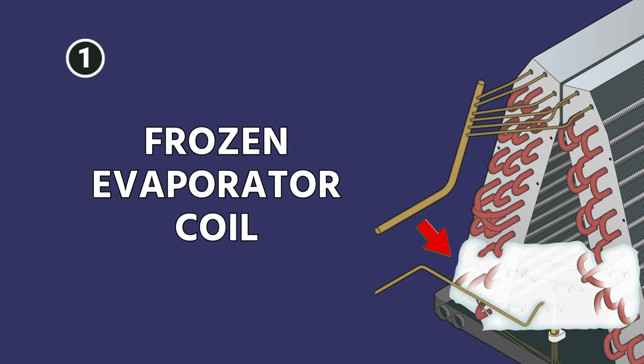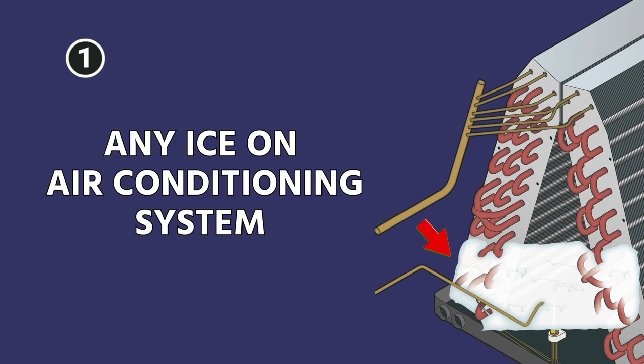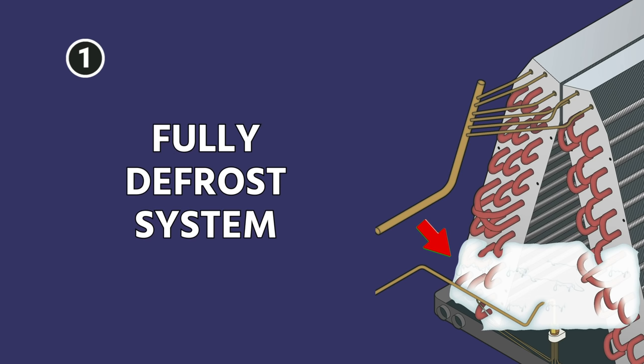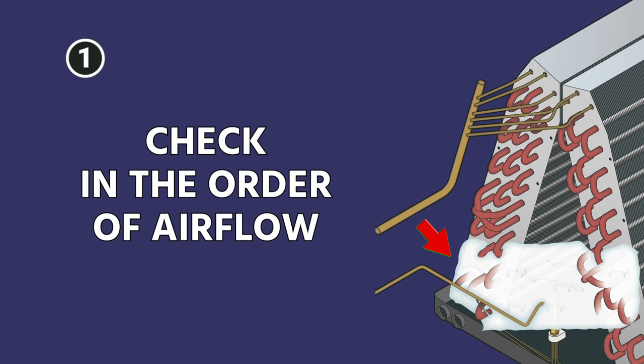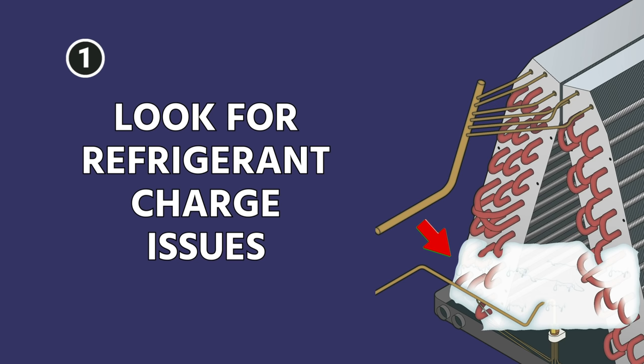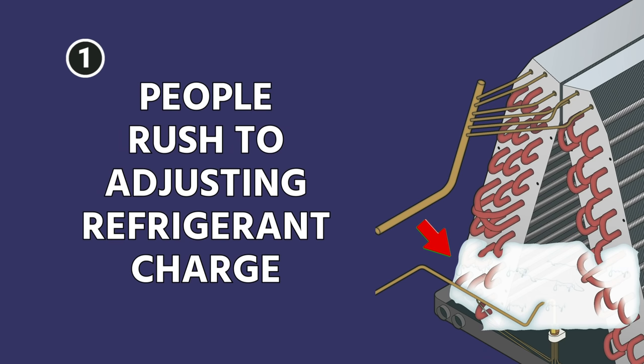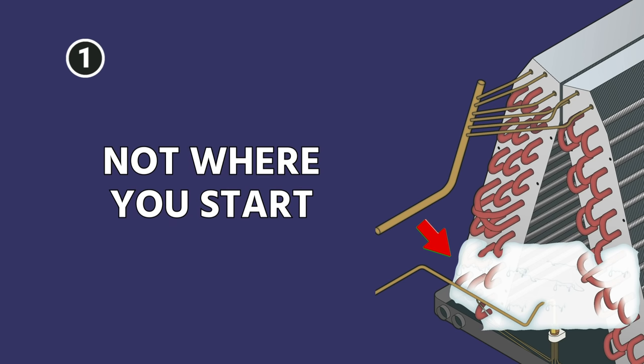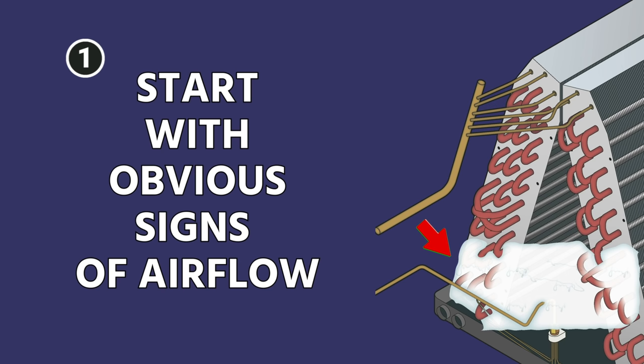So step one: if you do find a frozen evaporator coil or any ice on an air conditioning system running in cooling mode, first you need to fully defrost the system. Defrost the coil, then check in the order of airflow, then look for refrigerant restrictions, then look for refrigerant charge issues. So many people rush to adjusting the refrigerant charge — that is not where you start. Start with the obvious signs of airflow, then move forward from there.